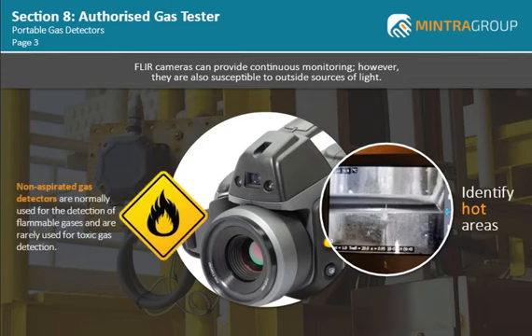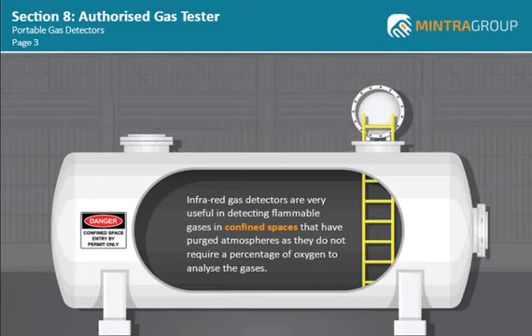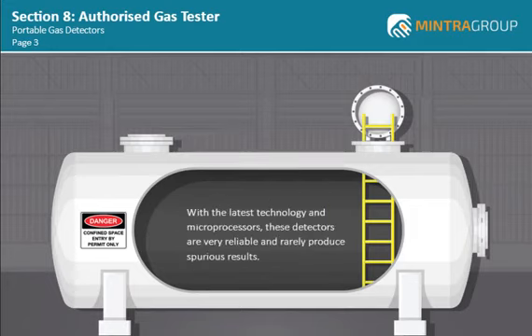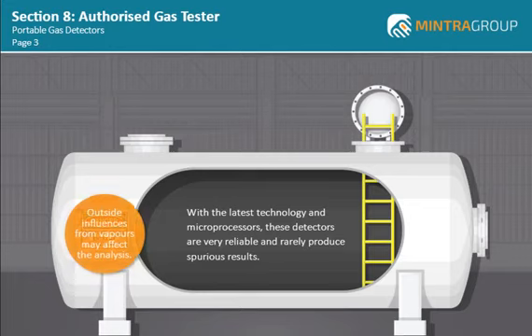Non-aspirated gas detectors are normally used for the detection of flammable gases, and are rarely used for toxic gas detection. Infrared gas detectors are very useful in detecting flammable gases in confined spaces that have purged atmospheres, as they do not require a percentage of oxygen to analyze the gases. With the latest technology and microprocessors, these detectors are very reliable and rarely produce spurious results. However, it is important that you are aware that outside influences from vapors, such as chemical cleaning fluids, may affect the analysis.